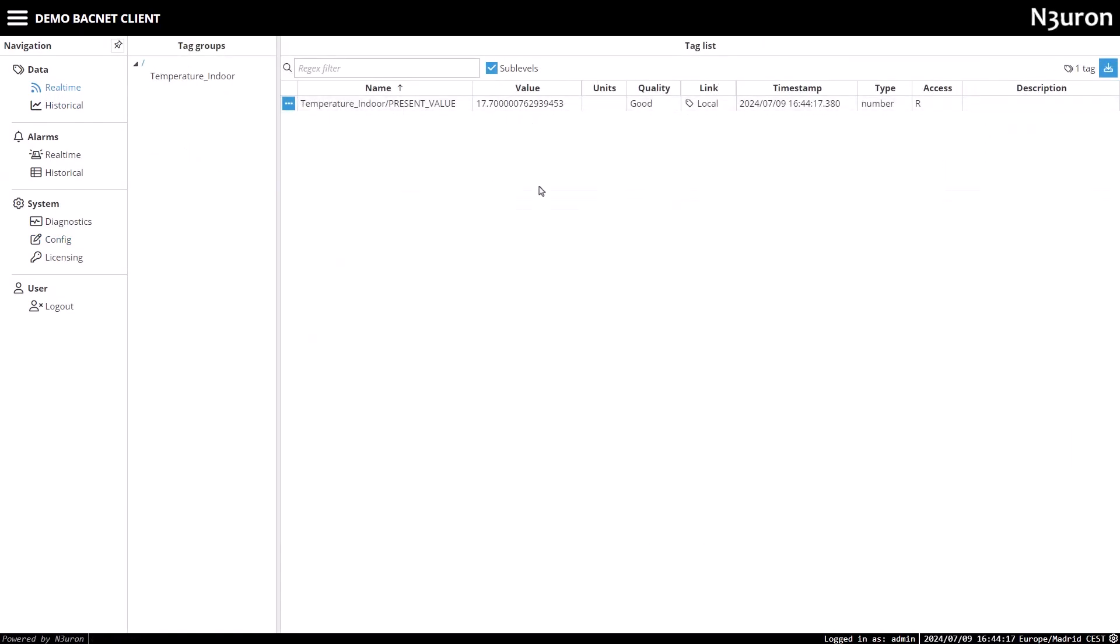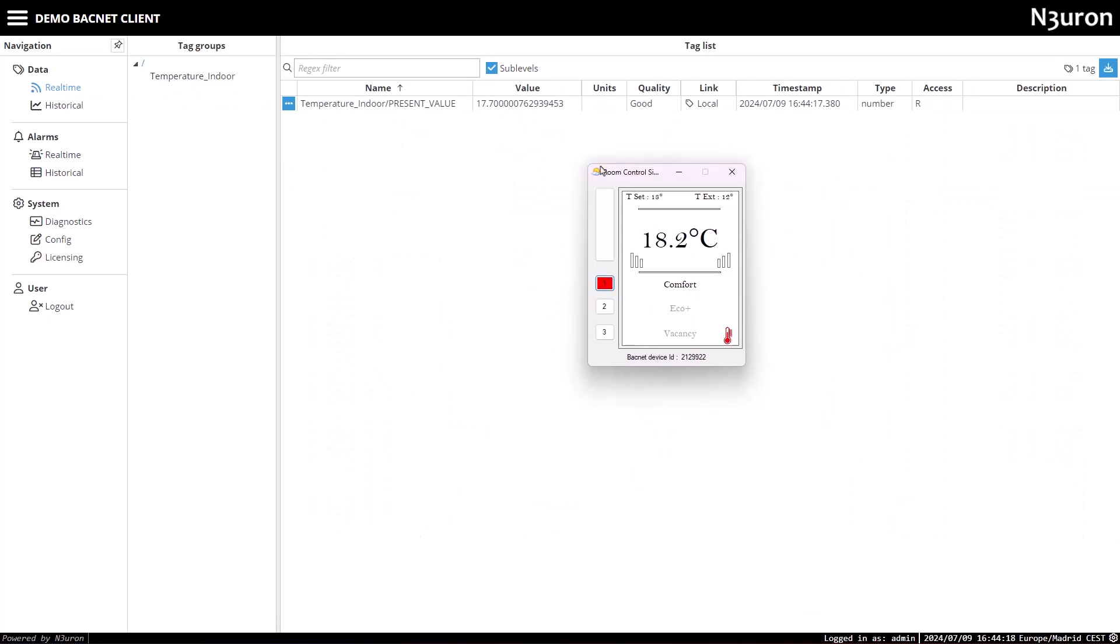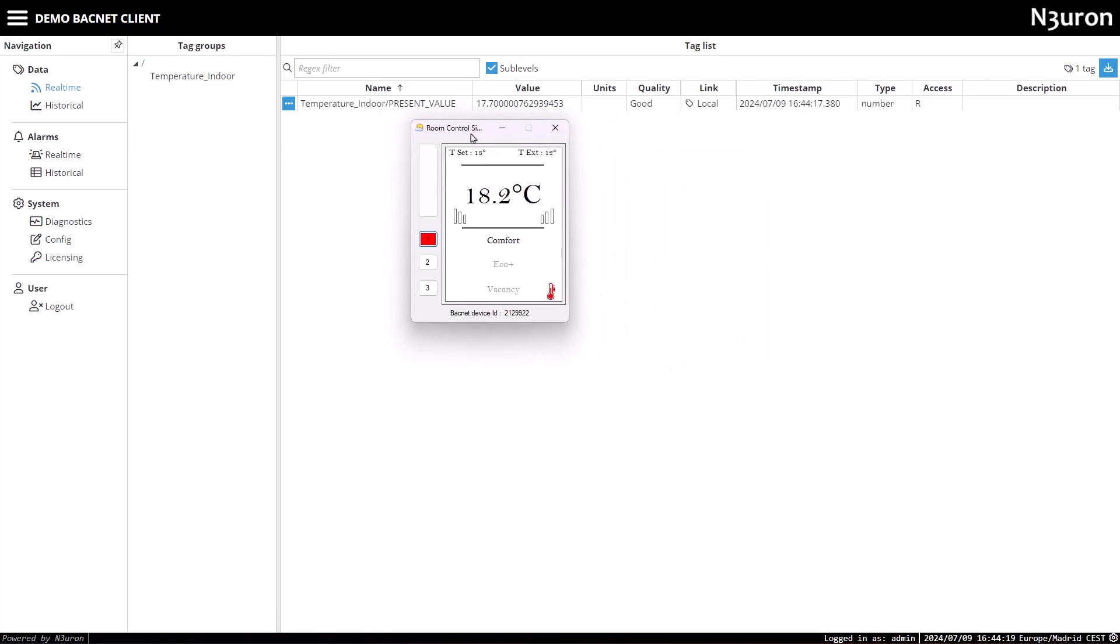Great. The tag reading for temperature indoor's present value is displayed correctly and with good quality. However, there's a noticeable delay between when the value changes and when it's read. This is because BACnet operates as a request response protocol.